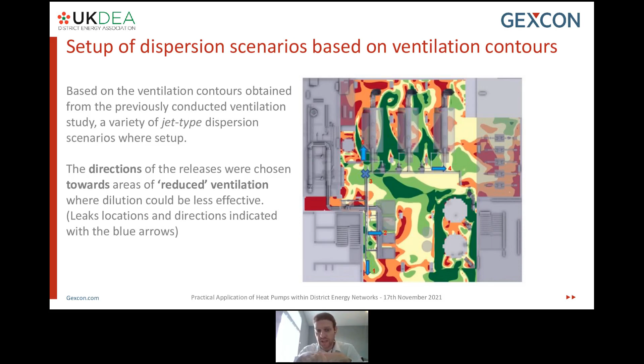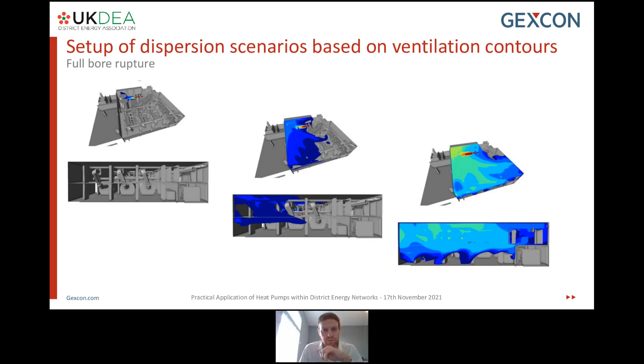This could be different release pressures, different hole sizes, and we obtain results visible in this picture, where the top left corner shows the early stages of the release, and moving towards the lower right corner, time advances, so the middle represents the middle stage of the release. For this particular case, a full bore rupture, it's a very drastic type of release, but for indication purposes it's quite clear to see how the gas advances and fills the room until it's nearly full. It's possible to see both top views and lateral views at the bottom of each corner.